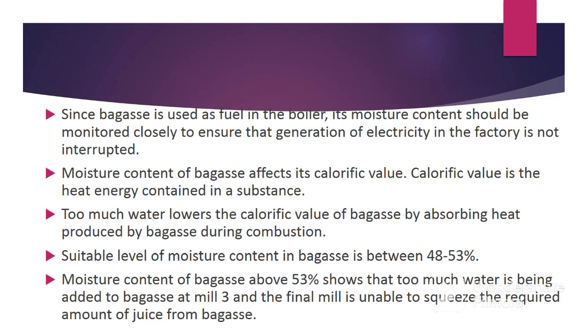Bagasse is used as fuel in the boiler, and its moisture content should be monitored closely to ensure the generation of electricity in the factory is not interrupted. As mentioned in a previous video, bagasse is burned in the boiler to produce heat energy. This heat energy is used to boil water to produce steam, and as the steam drives the turbine it produces electricity to be used in the factory. Moisture content of bagasse affects its calorific value, which is the heat energy contained in a substance.